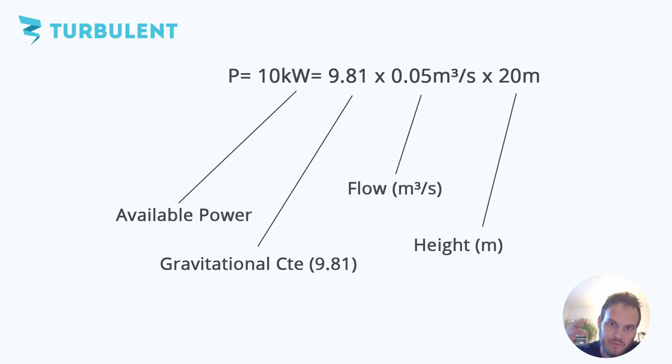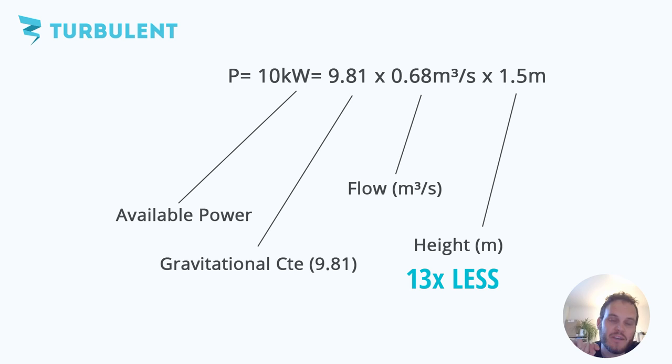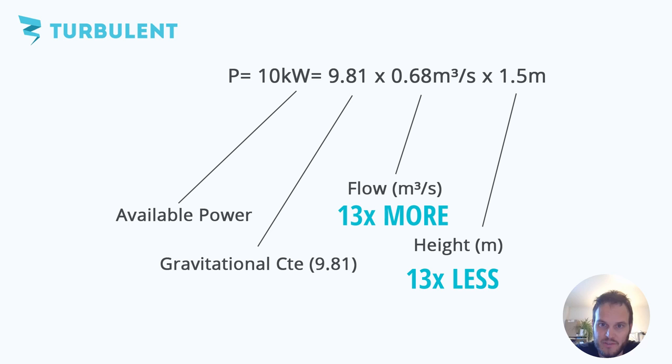If you then look at low head hydropower for instance our vortex turbines then you see that we have 13 times less height difference than the other example. For example we can use 1.5 meters of height difference to get to that 10 kilowatts but then we need to recalculate the amount of water that we also pass through that turbine. Recalculating that shows that we now need a flow of 0.68 cubic meters per second or 680 liters per second. This is of course also 13 times larger than with a high head case. So less head or less height difference means you need more water flowing through your turbine.